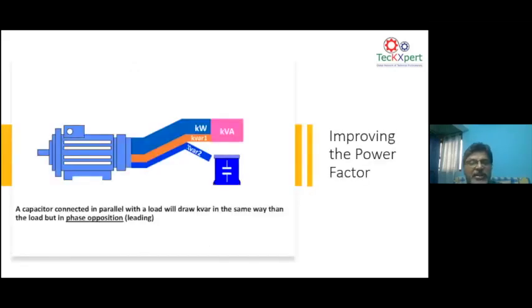Now in a normal power factor correction, what we always do is put in a capacitor bank, and when you put in a capacitor, a certain amount of reactive power is exchanged by the capacitor with the motor. How it works: the motor stores energy in the magnetic field, and in the capacitor, energy is stored in the electrostatic field. So between the magnetic field and the electric field, there is an exchange of energy. That is the role of a capacitor, because ultimately electricity and magnetism try to handshake and they go together. So if you put a capacitor bank for motor compensation, the motor will exchange energy between its magnetic field and the capacitor's electric field.